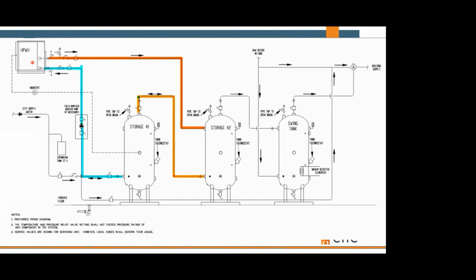Meaning when nobody's using domestic water and everybody's sleeping, that's when the heat pump water heater is doing its job. And what it's doing while everyone's sleeping, it's sending small amounts of hot water into storage tank number 2. It's also backfeeding into storage tank number 1 and continuing to send cold water back to the heat pump water heater, forgive me. Okay, so throughout the night, an 8 to 10 hour cycle, the goal is to get storage tank 2 and storage tank 1 up to temperature.